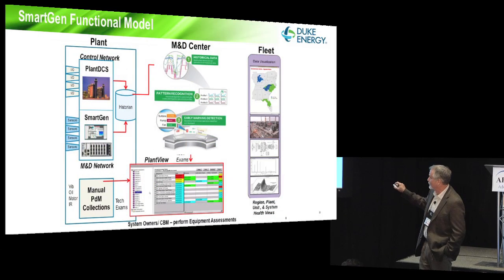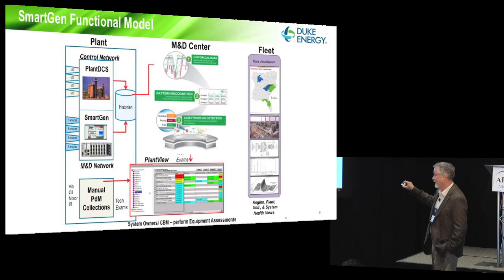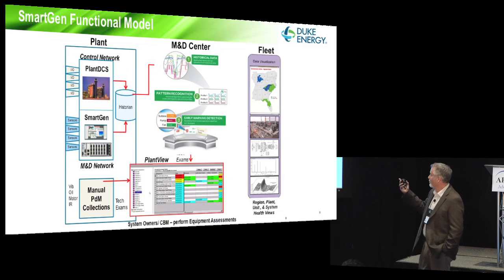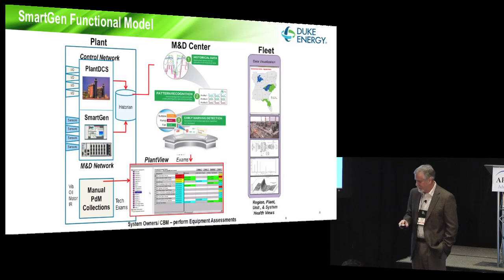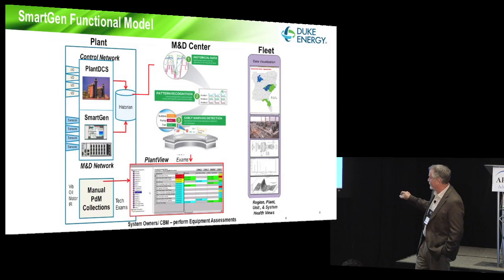There's the controls network - everything coming out of the DCS goes to the historian and ends up in our M&D center with the Prism modeling tool. All the new sensors we built are in this new M&D network that also ends up in the historian, adding new capabilities. Manual data still flows into a product called PlantView, an asset health management system where all the manual, online, and inspection information ends up.